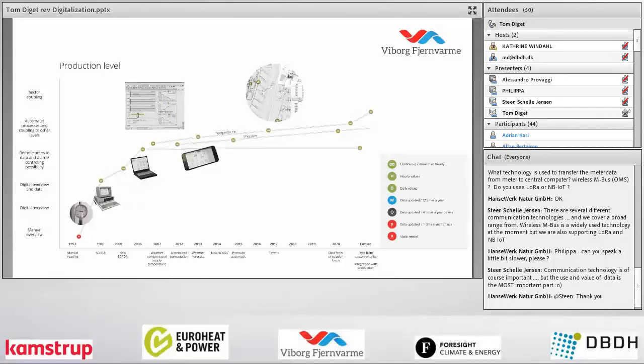In 2017, we installed a hydraulic control system called Thermis to control this supply temperature based on a load forecast and a calculation of the network temperatures in the distribution grid. This temperature automation has also been very feasible—we reduced our temperatures from around 95 down to today around 60 degrees in supply temperature.